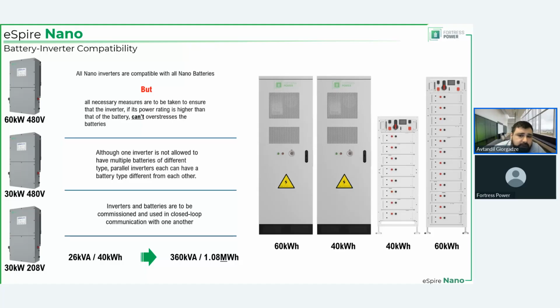Now, someone could be asking, well, if I need to be so careful, if I need to derate my inverter capabilities as far as battery charging and discharging goes, why would I bother having this type of system? Well, sometimes people want to go really extreme on the PV size and have it quite large, and the battery size doesn't matter to them that much, because much of that PV production is consumed while it's being produced, right? That type of thing.